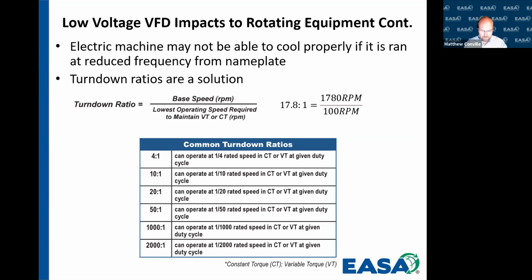So one of the last things that we want to talk about is actually the impacts of using a variable frequency drive and really slowing down the speed of the machine. When we look at the speed of a motor, if it has an integral fan, as the motor slows down, the flow is going to be reduced at a linear rate. It may not be linear, it may be more than linear, but it's going to be at least at a linear rate. But the other thing that we have to consider is we still have pressure drop inside of the machine. So not only are we limiting flow, but we may not be able to overcome the pressure drop that's needed, which basically means we're not going to move enough air across the windings, or in some instances get enough air across the bearings to actually keep things cool.